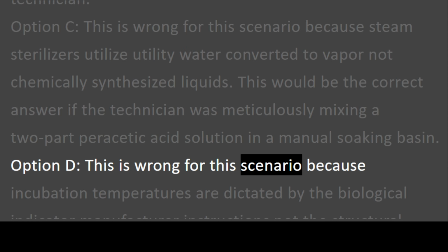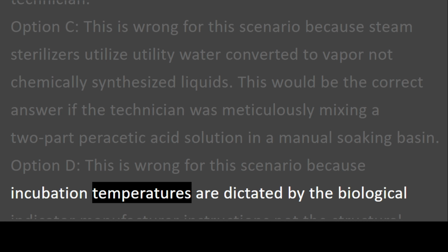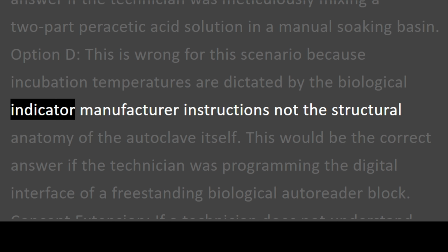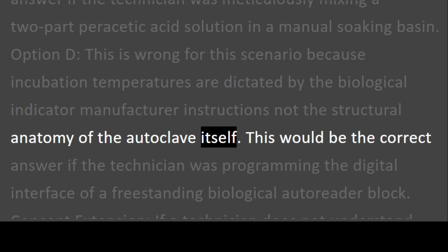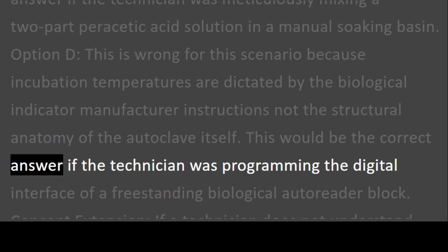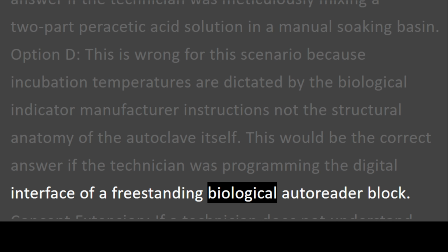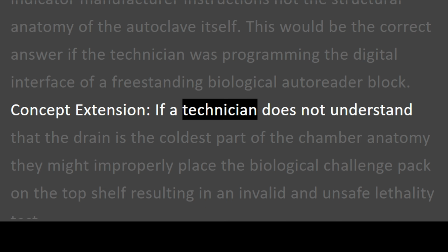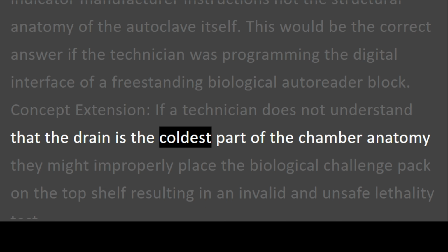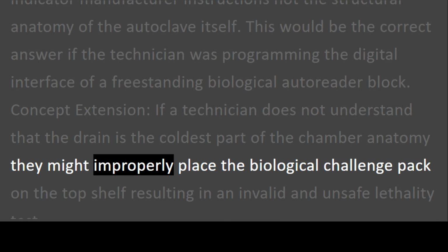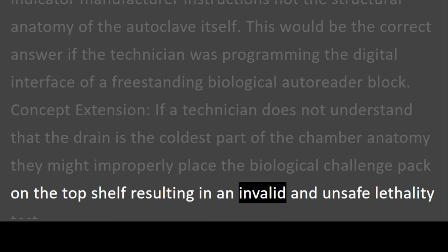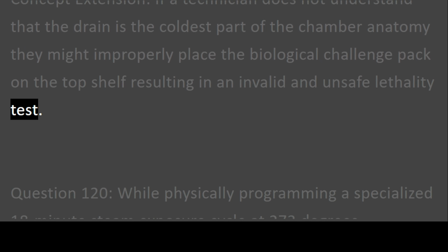This is wrong for this scenario because incubation temperatures are dictated by the biological indicator manufacturer instructions, not the structural anatomy of the autoclave itself. This would be the correct answer if the technician was programming the digital interface of a freestanding biological autoreader block. Concept extension. If a technician does not understand that the drain is the coldest part of the chamber anatomy, they might improperly place the biological challenge pack on the top shelf, resulting in an invalid and unsafe lethality test.